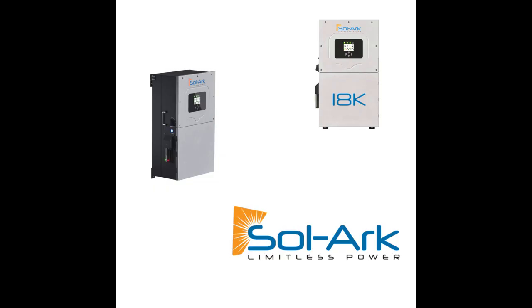Then we have the gen port on the AC side, which is a multi-function connection, named for generator connection. You can connect any generator as long as it matches the voltage of the inverter you're connecting to. For example, our residential units are 120/240. As long as it's a 120/240 generator, you will be able to connect it to the gen port. And this adds a tertiary source of power for off-grid resilience. For customers that don't build heavily on the battery storage side, you're still able to have a functioning system off-grid that's fully autonomous. And we typically don't recommend building past 24 hours of backup, just because it's more cost effective at that point to add a generator.